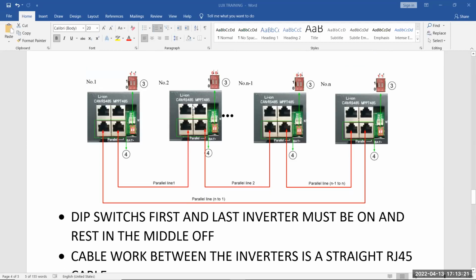Now, if there's 2 inverters, both small white switches on these red resistors must be in the on position. So the first one is on and the second one is on. But if there's more than 2 inverters in this string that you put in parallel, the first one and the last one are on, the middle one is off. Now this resistor tells my units which unit is the first and the last in the parallel line. So it knows how to loop back the information between the first inverter, that's my master, and the last inverter. So that just tells it basically you're number 1 and you're the last one.